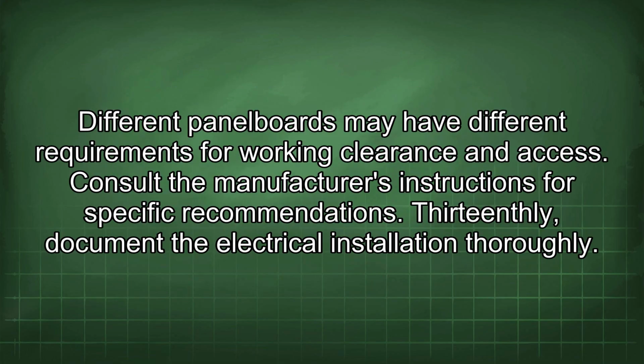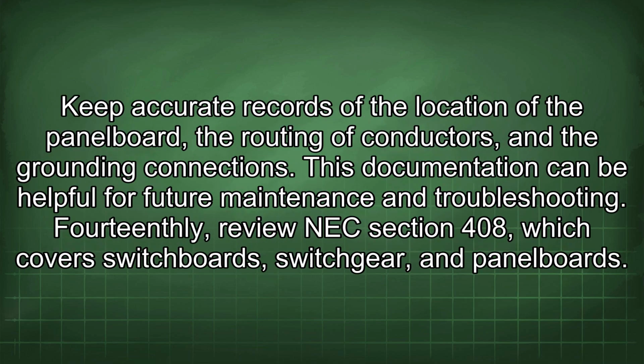Different panel boards may have different requirements for working clearance and access. Consult the manufacturer's instructions for specific recommendations. 13thly, document the electrical installation thoroughly. Keep accurate records of the location of the panel board, the routing of conductors, and the grounding connections. This documentation can be helpful for future maintenance and troubleshooting.